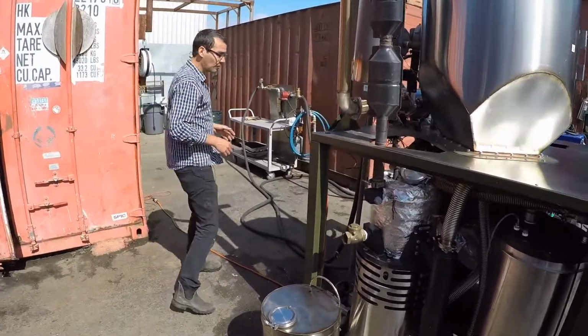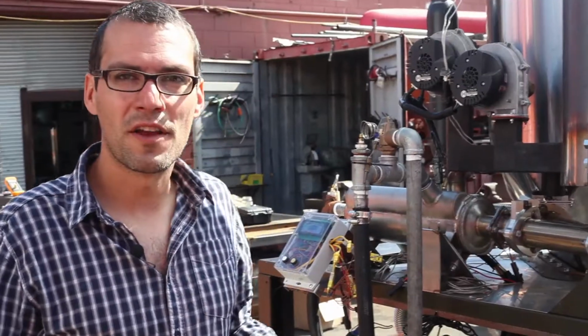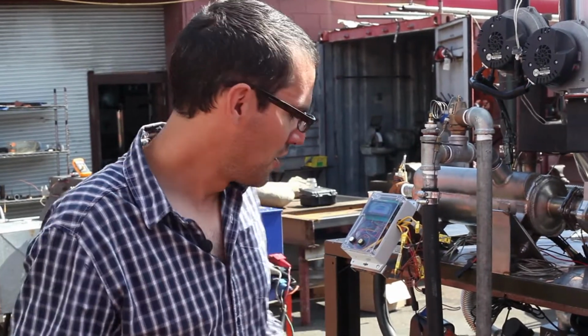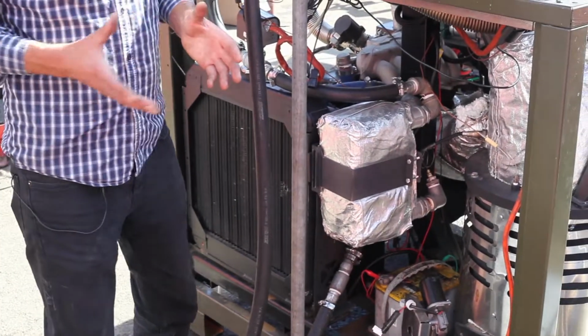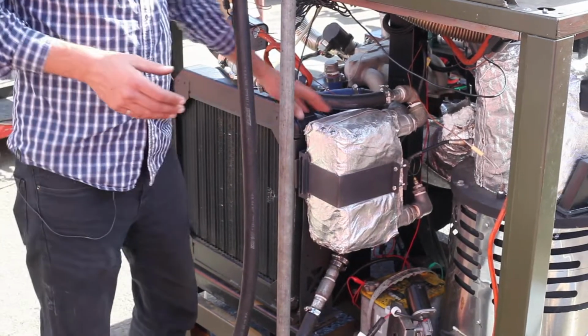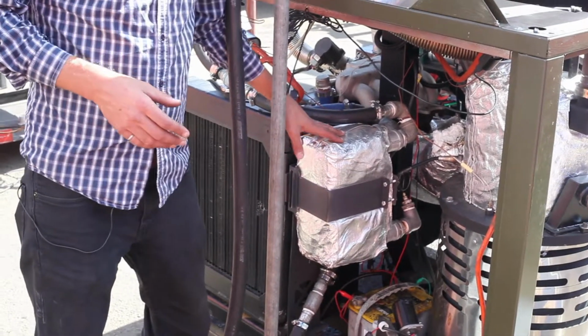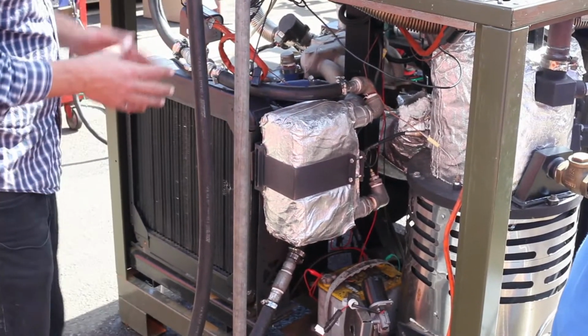The CHP system takes water in at 60 degrees Celsius and delivers it out at 80 degrees Celsius. And it heats that water up 20 degrees in two stages. First, through a plate heat exchanger that's taking heat from the engine coolant water and exchanging it with the CHP system to raise the water temperature up about 10 degrees.